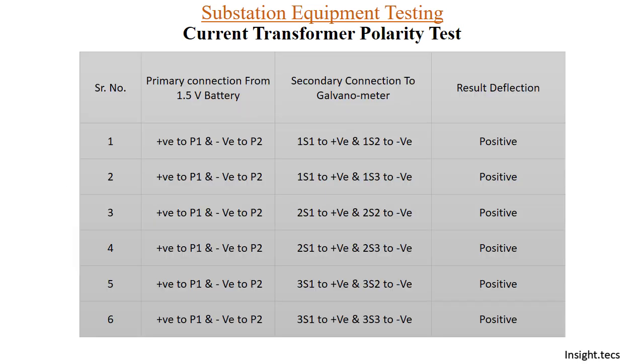This is the conclusion table to test the polarity of the CT. For primary connections, positive is connected to P1 and negative to P2. On the secondary side, 1S1 is connected to positive and 1S2 to negative, and the result will be a positive deflection. You can follow this schedule to check the CT polarity test for all cores.